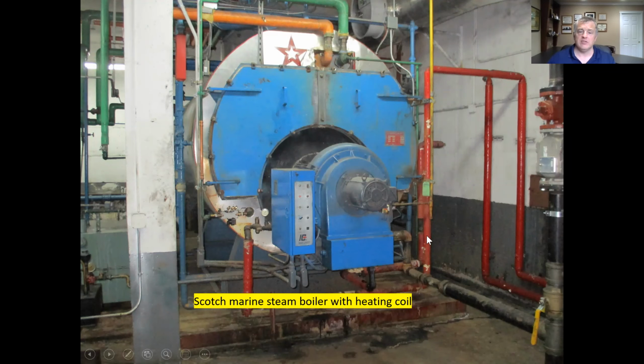But not so fast. We take that same heat we've produced and that same steam, and we send that steam out in these two pipes at the top, cool it down a little bit, and make it hot water for sinks and showers. So this one unit provides heat and hot water. Very common in a lot of these buildings.